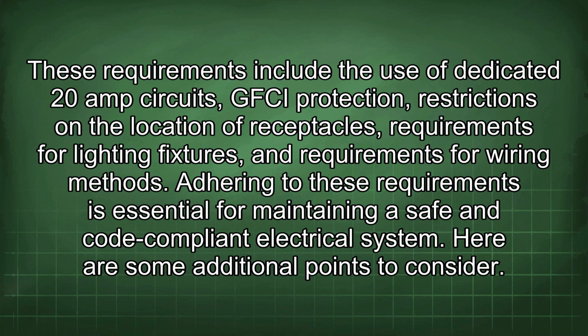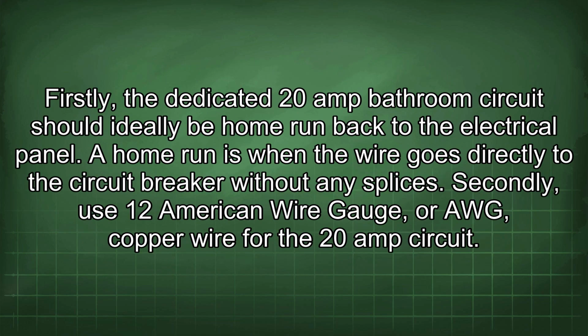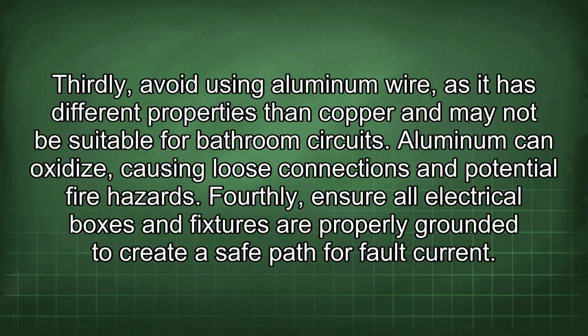Here are some additional points to consider. Firstly, the dedicated 20-amp bathroom circuit should ideally be home run back to the electrical panel. A home run is when the wire goes directly to the circuit breaker without any splices. Secondly, use 12 American wire gauge, or AWG, copper wire for the 20-amp circuit. Thirdly, avoid using aluminum wire, as it has different properties than copper and may not be suitable for bathroom circuits. Aluminum can oxidize, causing loose connections and potential fire hazards.